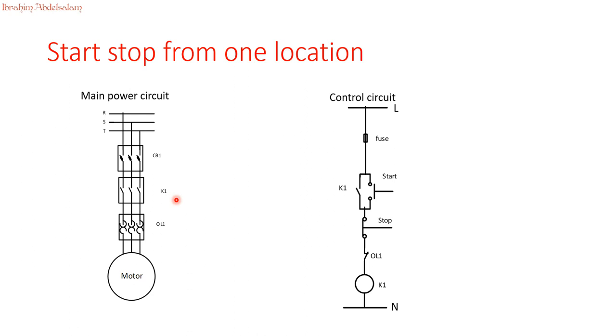We use the overload signal as feedback so we can interrupt and turn off the contactor. We have one start button and one stop button. Here is the fuse we use to protect our control circuit. Once start is pressed, the current will flow through the switch to the stop button, through the overload contact, to the contactor coil. The contactor coil will be energized, and the contacts will change position from open to closed, so current flows to the motor — the motor is now running.